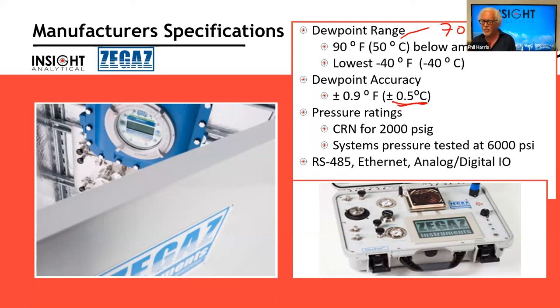For Canadians, we have CRNs for up to 2,000 pounds. Systems are pressure tested to 6,000 pounds. RS-485, Ethernet, analog and digital IOs. A nice user interface. You get to see right on the screen what's the temperature, what's the pressure, which dew point did I just hit last.